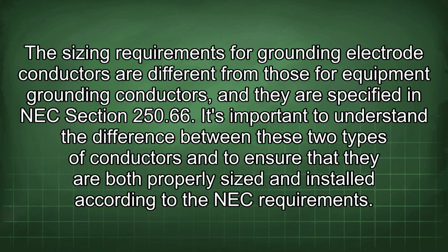The sizing requirements for grounding electrode conductors are different from those for equipment grounding conductors, and they are specified in NEC section 250.66. It's important to understand the difference between these two types of conductors and to ensure that they are both properly sized and installed according to the NEC requirements.